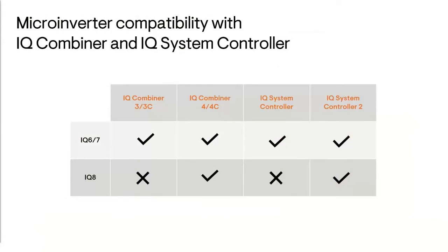Here's a simple table regarding compatibility for you to reference. The IQ8 can only be installed with the new IQ Combiner 4 or 4C and IQ System Controller 2. If it's installed with earlier versions, it won't be code compliant. The IQ6 and IQ7 are compatible with both the new versions and old versions. If you want to keep things simple, you can always order just the new versions, and they can be used for both new installations with IQ8 or retrofitting existing systems.